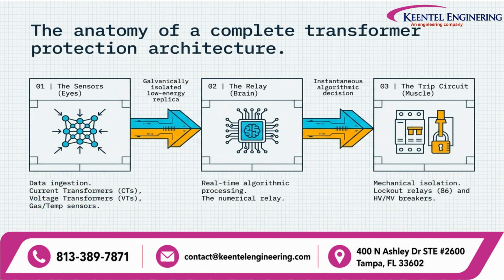Let's now look at the three fundamental layers of a complete transformer protection architecture. The first layer is the sensors. Current transformers, or CTs, voltage transformers, or VTs, and transformer condition sensors provide the raw information required by the protection system. The second layer is the relay. The numerical relay receives those measurements and performs real-time algorithmic processing.